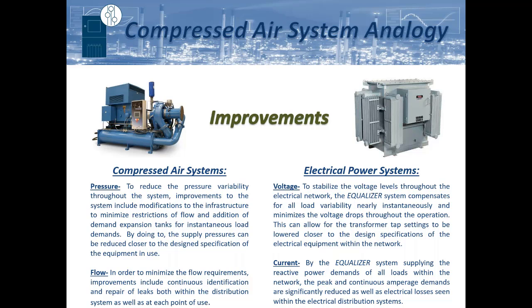And in essence, that's exactly what an equalizer system is. So an equalizer system can provide that instantaneous demand for reactive power in such a way that it provides a stable pressure on that network throughout, a stable voltage level. So as with a compressed air system, where although all of the components within that system may require a 90 psi pressure, oftentimes you may see it running at 100 or 110 psi because in order to account for those pressure fluctuations and not impact the process.